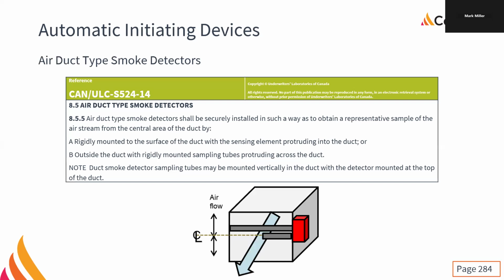We want to install the duct smoke so that we're getting a representative sample of the airstream. So we're going to put it through the middle of the ductwork, and we're going to make sure that it's rigidly mounted because we don't want the air sampling tubes to bend under the wind. Generally speaking, if the duct is 3 feet or more wide, we put the air sampling tube right through to the other end so it can get supported by the other side of the ductwork, and we just put the cap on it. Again, depends on the insulation, and then it's really easy to figure out because the air sampling tube has holes in it for actual sampling, and you just point them into the wind.